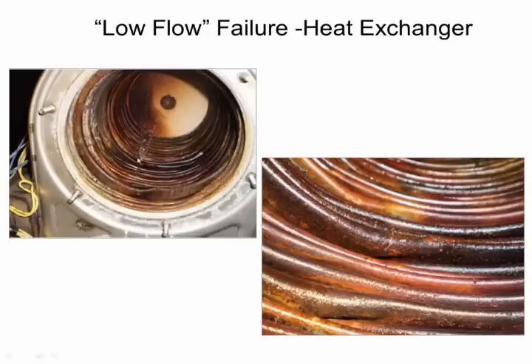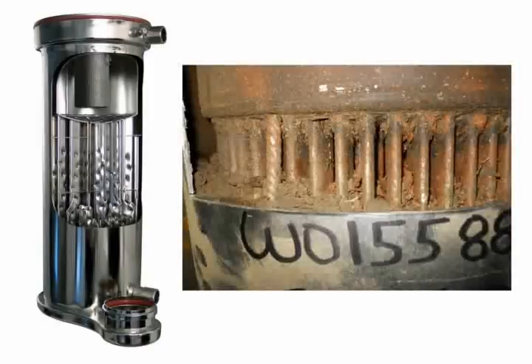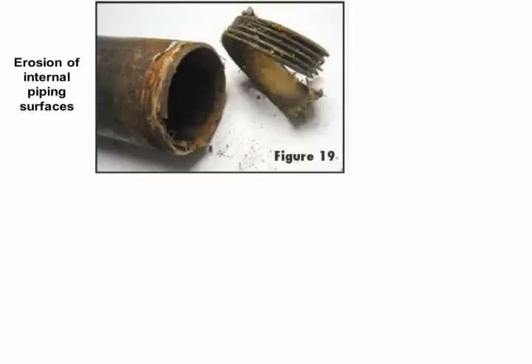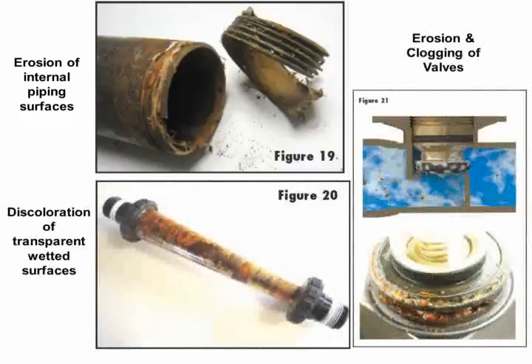Here's a section of a condensing boiler with the plate pulled off, and you can see what's going on. It failed. And if you look real closely, you can see water that's actually spurting out of the copper tube there. Now, whether this succumbed to the effects of rust, basically, or if it was a combination of rust and limescale, it's hard to say. But in the end, it created dissimilar stresses on that, and it failed. And here's another heat exchanger, different type, another very good heat exchanger, but with the inappropriate water conditions and treatment of air and dirt in the system, a failure.